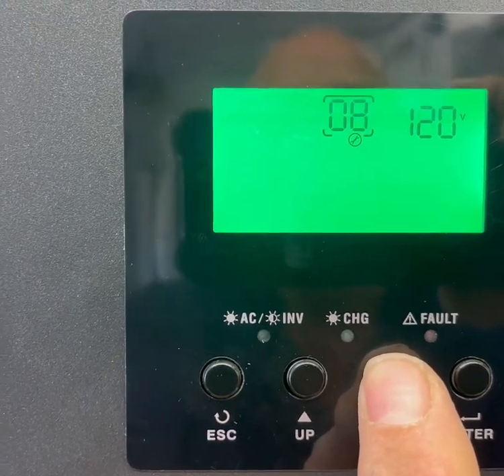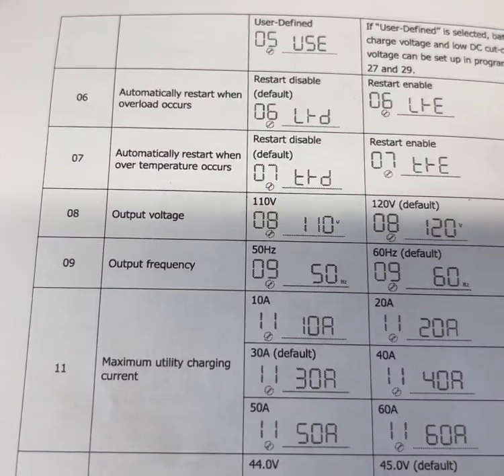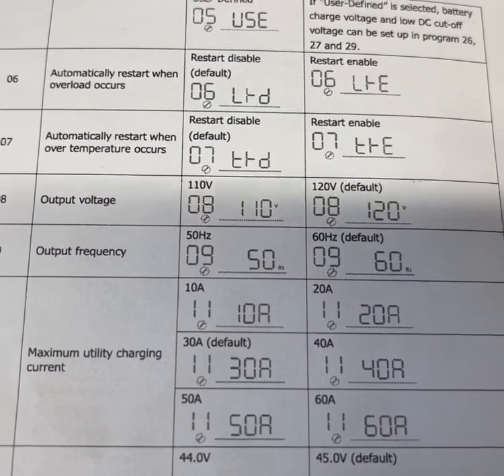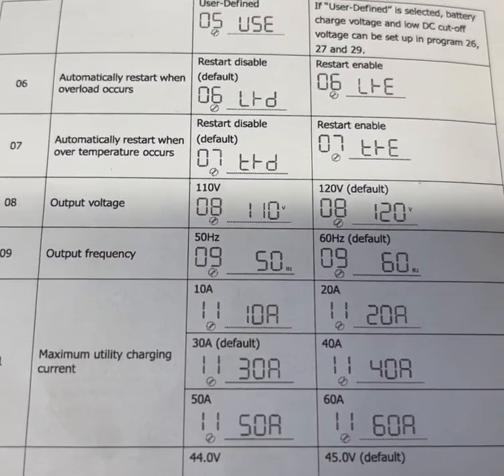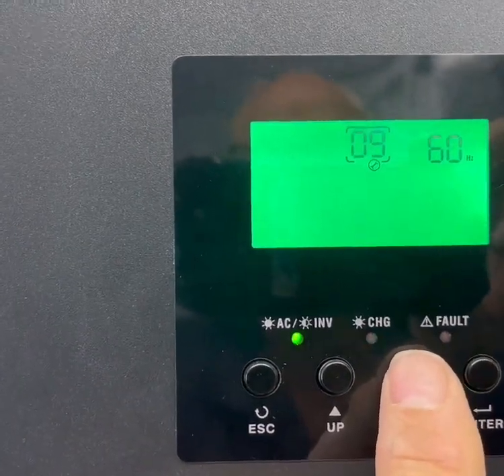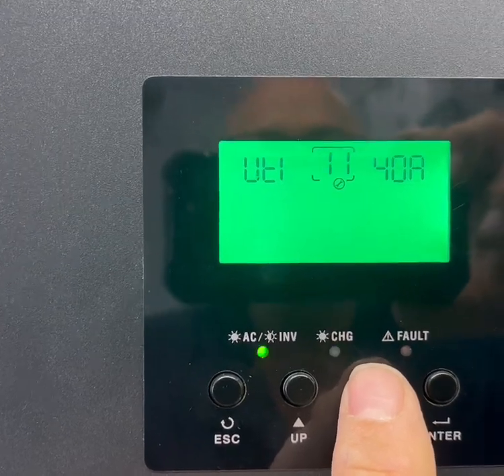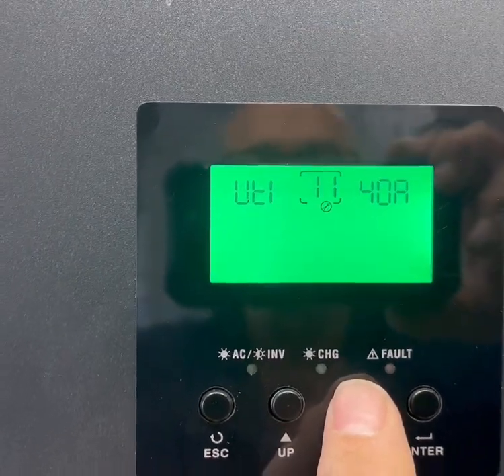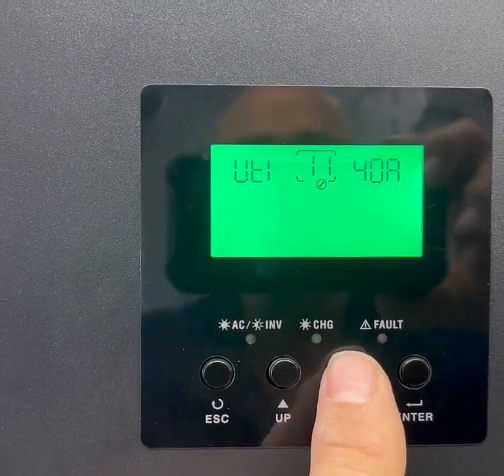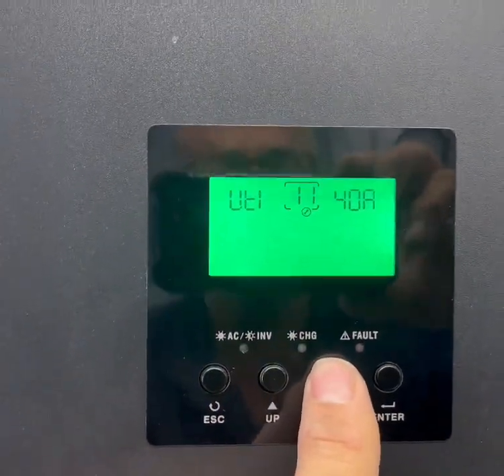Number eight is our output voltage coming off each leg — the default is 120 volts, and we left that at 120 volts. Number nine is 60 hertz, which is standard in North America — Europe and other places use 50 hertz, which I understand is a little more efficient. For utility charging, number eleven, we have that set at 40 amps, though we're not really using utility much.